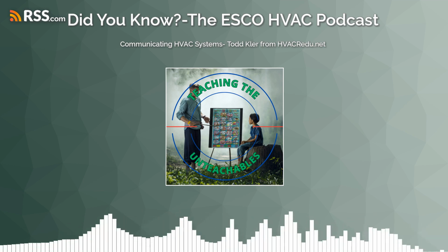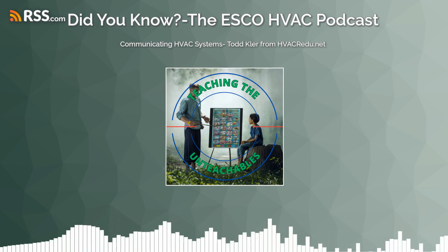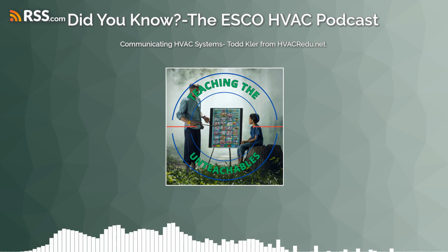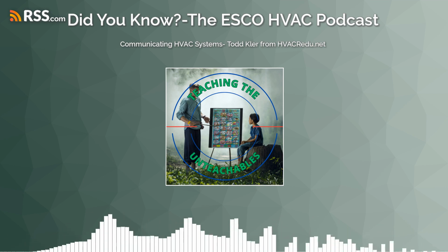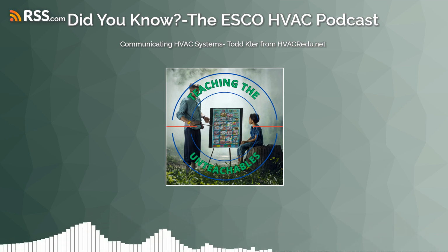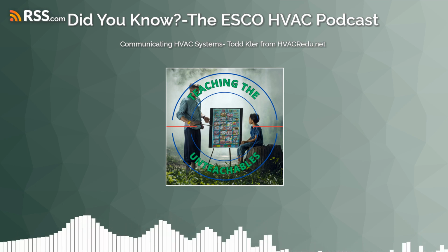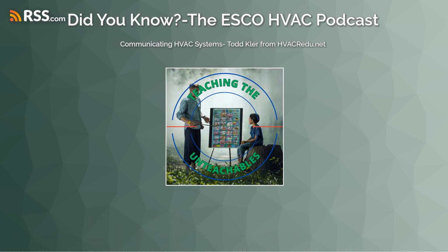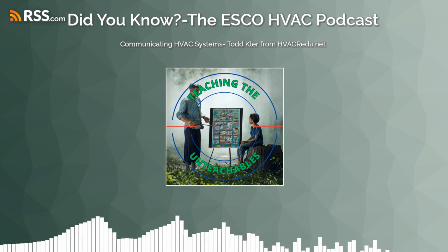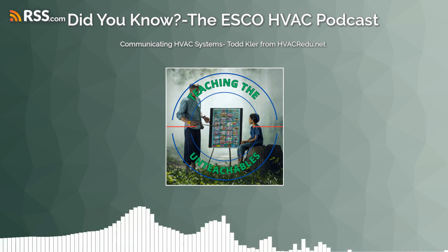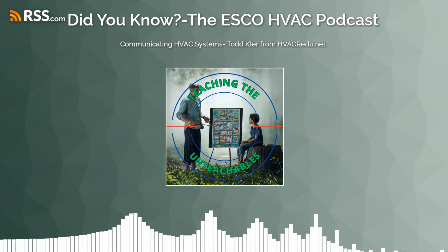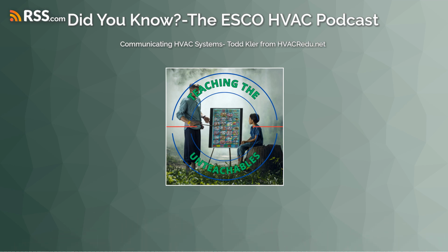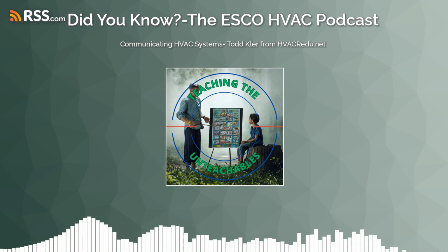So yes, DX negative to common. That is common, 24 volts. So we're just on 3 volt DC. We're going to see 3 volts on both of them. And if we don't, we got to disconnect, and we got to start seeing where we're losing it. So the best way on any communicating system, disconnect your control wires, start at that indoor unit, verify you got good voltage coming from it, and then start adding them one at a time.